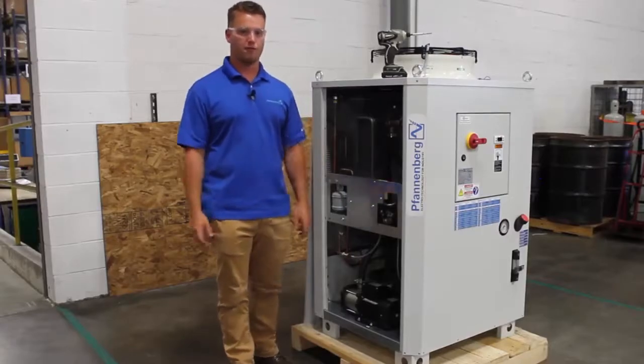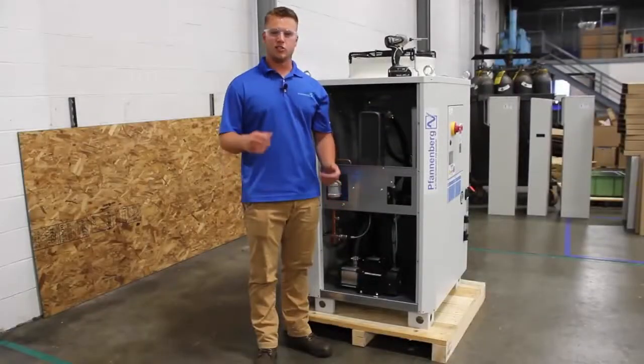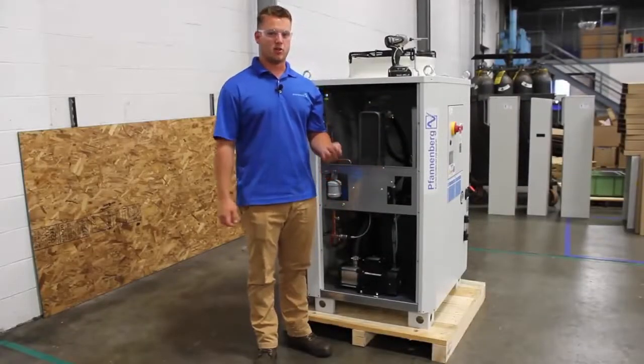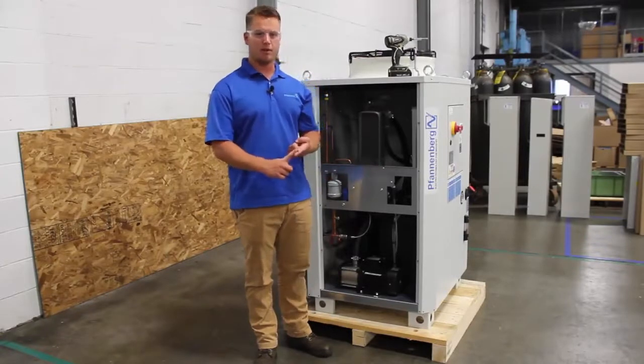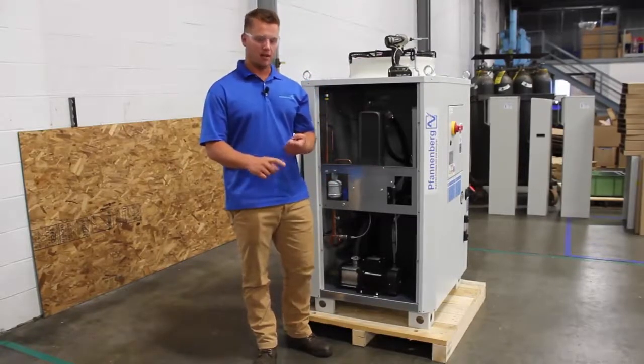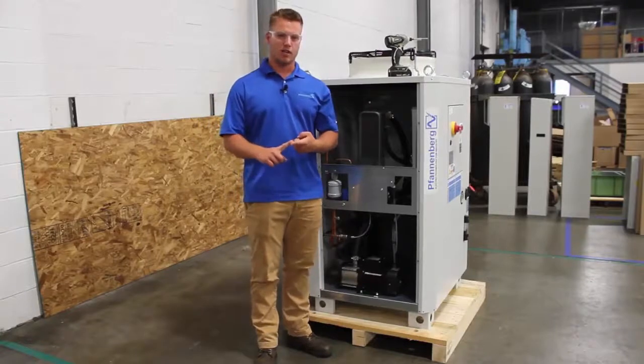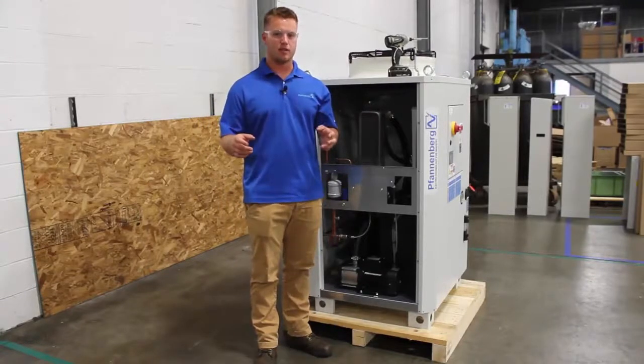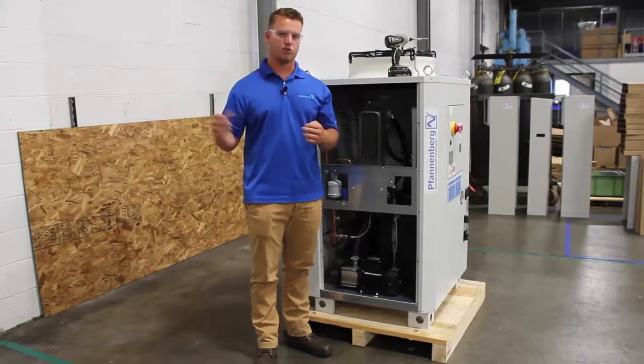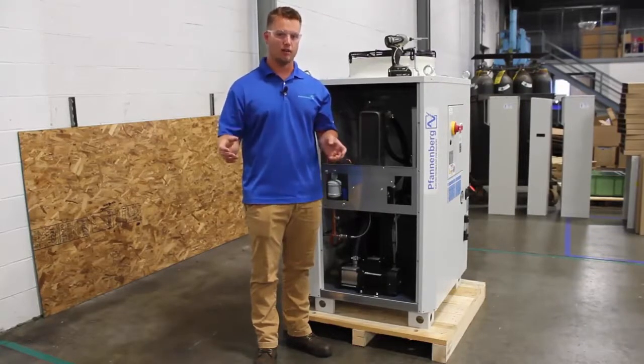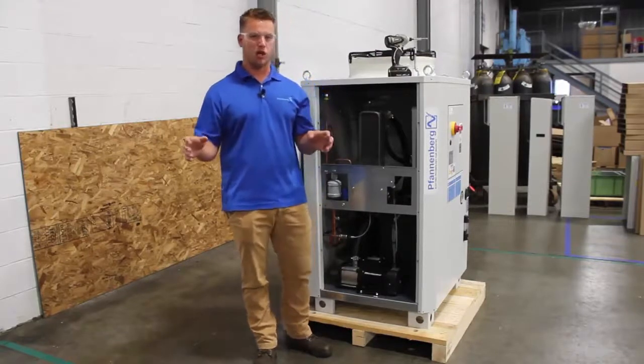All right, so this chiller also comes standard with 2 safeties that'll protect the pump so it doesn't get burned up on you. Number 1 is going to be a flow switch. If the pump for whatever reason stops, that flow switch is going to stop and it's going to pull the contactor out so the pump does not continue to run. This protects the pump from running dry. We never want the pump to run dry.